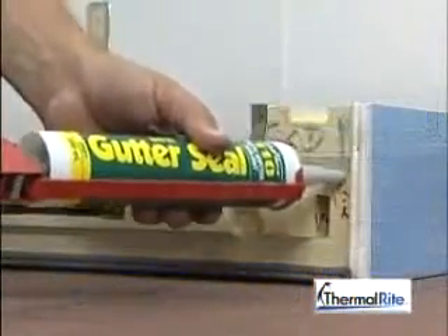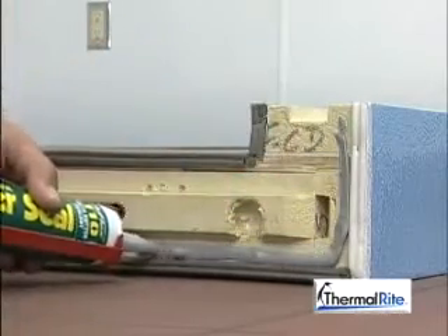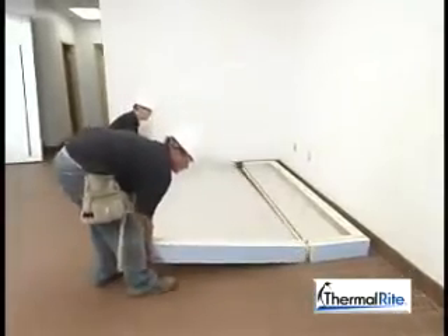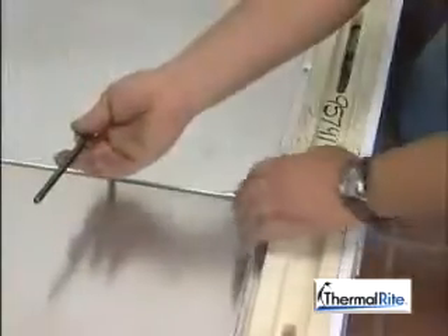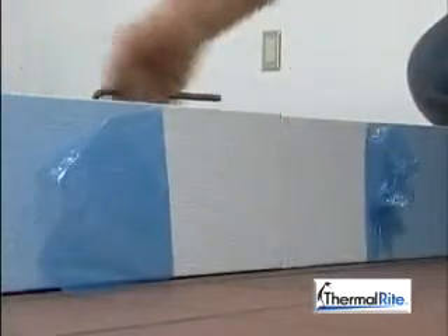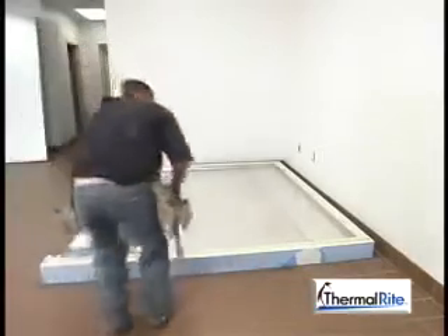Remember, if the walk-in is for a freezer application, ThermalRite recommends that caulk be used between the floor panels and all exterior wall and ceiling panel joints. Use a 5/16-inch hex wrench provided to cam lock the floor panels together. Make sure that the ends are flush. Tighten each cam lock to a dead stop. You will be able to feel the cam lock bring the panels tightly together. For cam lock walls to floors, follow the same steps for walls to ceiling installations.